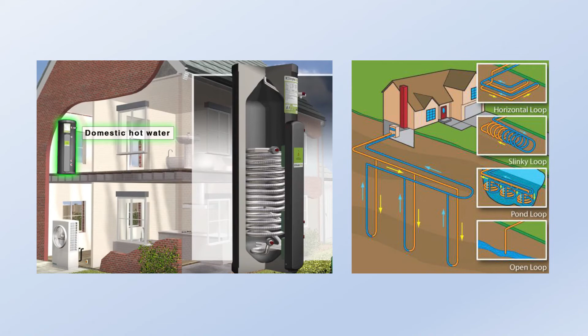So if you've got a big area of underfloor heating, you'd have the heat coming out at about 35 Celsius, and then the returning temperature is about 27 Celsius. So it's very low grade heat. So what a heat pump is doing is moving low grade heat, compressing it, and then moving that compressed heat to a different place where it's been moved.